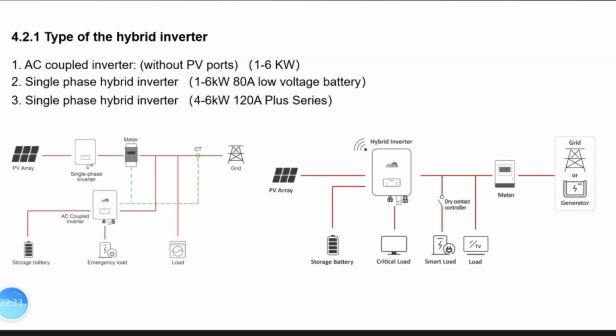Here are our models for the single-phase hybrid inverter. Right now we have 3 series. One is the normal version from 1 to 6K. It's 80 amps. Amps is the discharge and charge current. And also we introduced the new plus version from 4 to 6K. The discharge and charge current is 120. So compared with the normal version, the plus version has more capacity to deliver power to the EPS loads and more power discharge and charge capacity for the batteries.